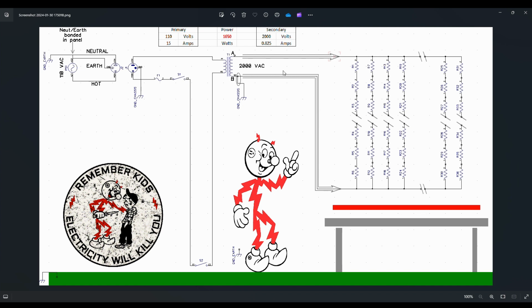Oh, something else I probably should have put a calculation here. The industry standard and the mil spec, the military specification for dielectric insulation, dielectric withstanding voltage, used to be 2.5 times your working voltage. Okay, so 2.5 times 2,000 is 5,000. So the insulation you've got on this wire should be at least 5,000 volts.